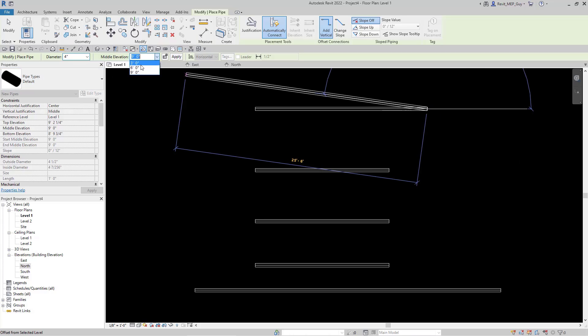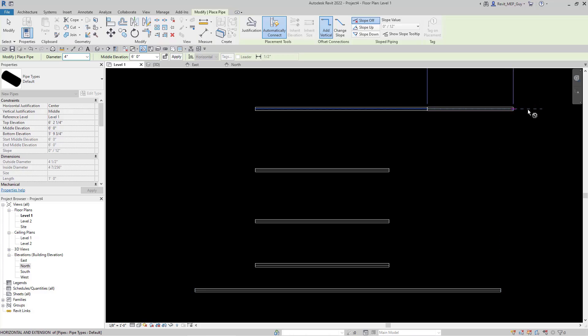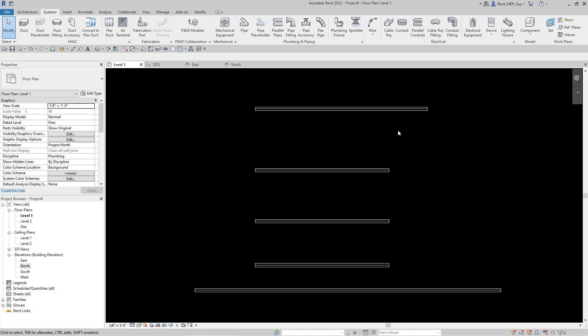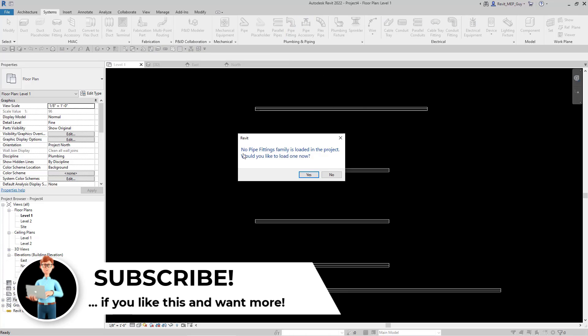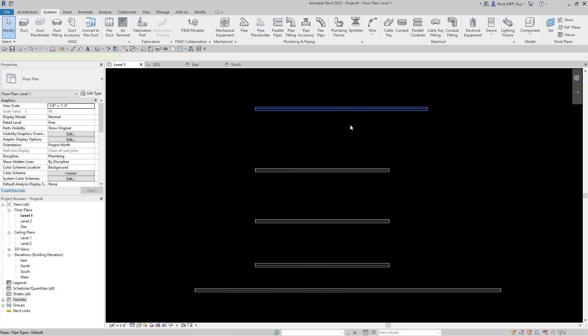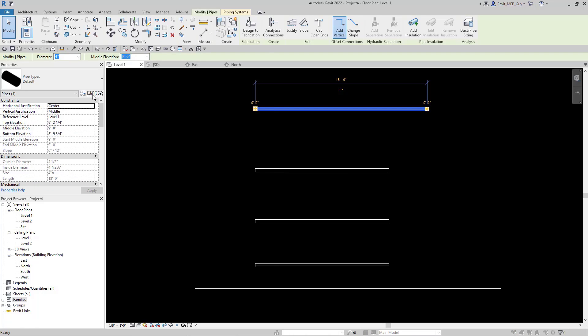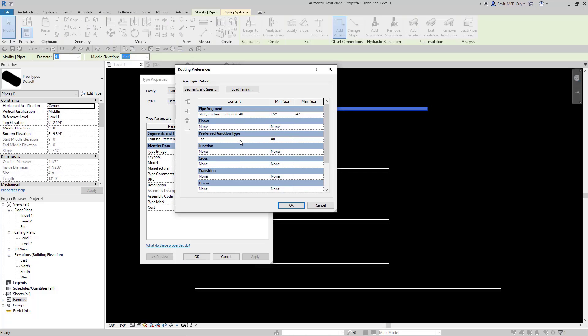Let's see if we try to increase or decrease the elevation — let's go to six feet. Again, you'll see that Revit's not allowing me to click and draw this pipe. The reason it's doing that is because there are no fittings loaded into this project. There's a couple of ways to check — one way is to go up to Pipe Fittings and click it. You'll see Revit says 'No pipe fittings are loaded into this project. Would you like to load one?' If I click on my pipe, go to Edit Type, go to Routing Preferences and click Edit — as you can see, there is no elbow loaded, no T, no junction, no cross. None of these fittings are loaded for my pipe, so anytime I try to draw any of these fittings, Revit doesn't know what to draw.